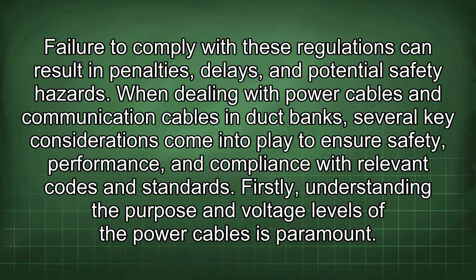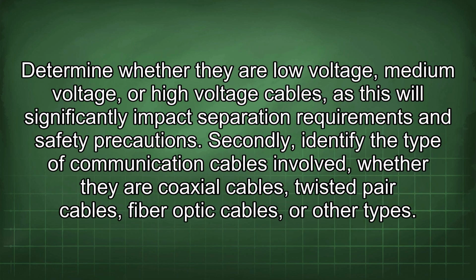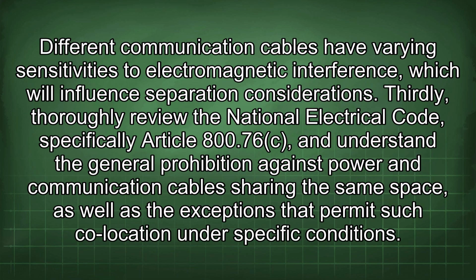When dealing with power cables and communication cables in duct banks, several key considerations come into play to ensure safety, performance, and compliance with relevant codes and standards. Firstly, understanding the purpose and voltage levels of the power cables is paramount. Determine whether they are low voltage, medium voltage, or high voltage cables, as this will significantly impact separation requirements and safety precautions. Secondly, identify the type of communication cables involved, whether they are coaxial cables, twisted pair cables, fiber optic cables, or other types. Different communication cables have varying sensitivities to electromagnetic interference, which will influence separation considerations.